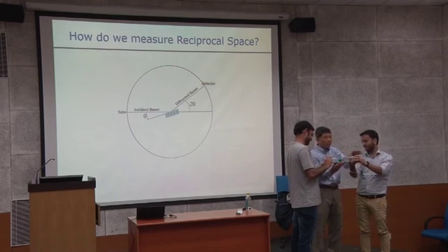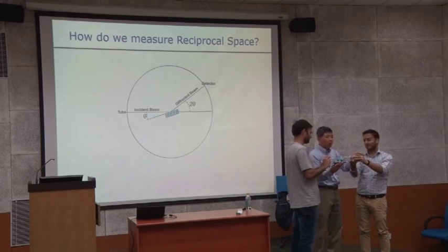But here, this guy is the X-ray tube. What is attached to the X-ray tube? Water line. High voltage, water line, everything is attached to here. And everything is perfectly aligned with the tube. And these heavy, bulky ones, you don't want to move every time.